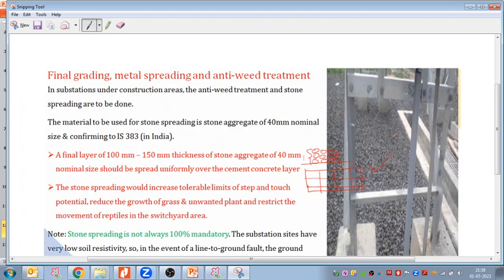So if any fault happens, say we have RYB phase conductors, and if any conductor is broken and touches the ground, if any line to ground fault happens, the fault current will flow into the ground, and this fault current will flow into the common grounding grid. And if we have no stone, there is a possibility that the fault current, or the potential rise of the ground due to this fault current, may be dangerous to a person walking above the ground.